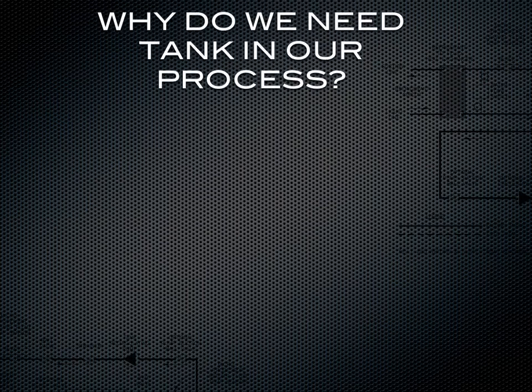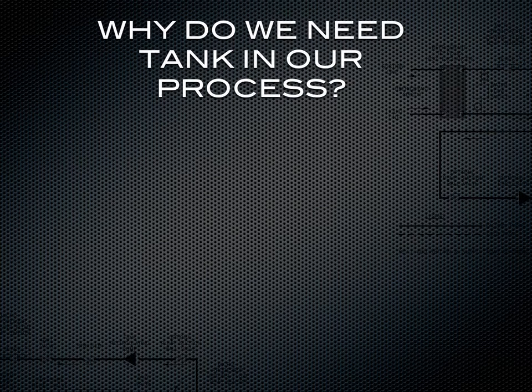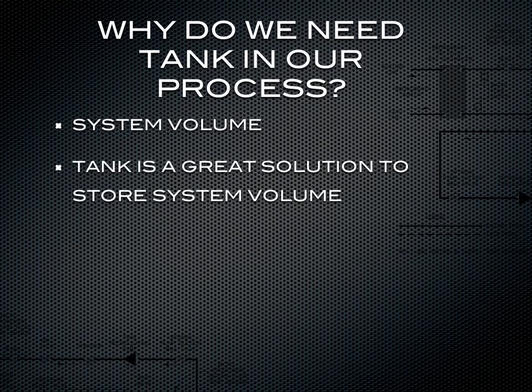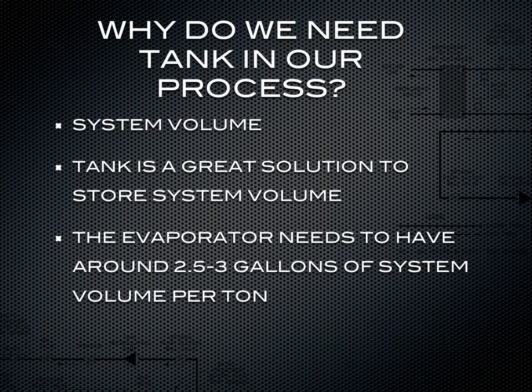Why do we need a tank in our process? One of the main reasons is for system volume. If you don't have enough piping between your chiller and the piece of equipment you're trying to cool, a tank is a great solution for that. A tank really just acts as a big piece of pipe. The reason we need system volume is to satisfy the chiller evaporator. The chiller evaporator needs around 2.5 to 3 gallons of system volume per ton somewhere in the system — that can be in a tank, in piping, or in both.